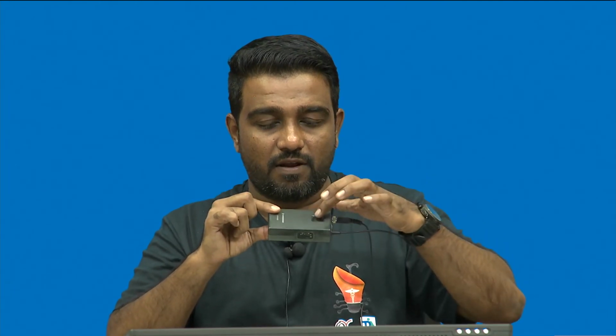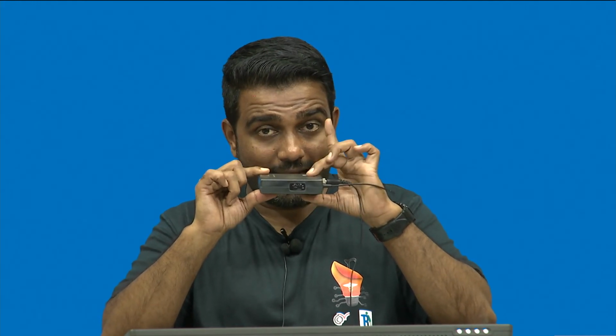But if I want to create a diaphragm, let me give you an example. If this is the wafer and this is the sensing area, I want to create a diaphragm exactly on the back side of this sensing area. That means I should align it on this side. How would I know it is perfectly aligned with the front side? That is what is called front to back alignment. I want to create a diaphragm exactly below this particular sensing area. This is where your front to back alignment will work.